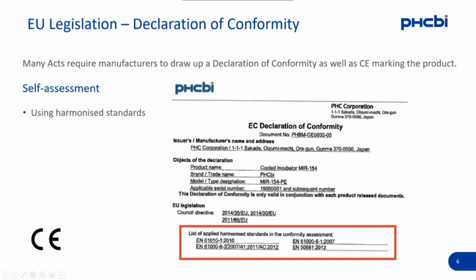And the most well-known of these is what's called EN 61010, which is the safety standard specifically for laboratory equipment. That's how the factory tests the products against this standard to confirm that the electrical risks are acceptable, and also the mechanical risks as well. Okay. So that's a declaration of conformity for a product that we have self-assessed using harmonized standards.